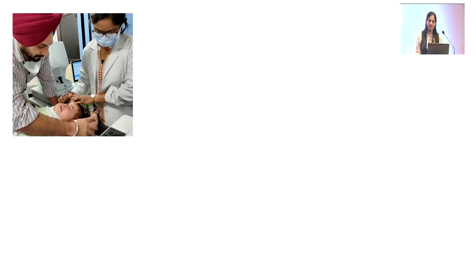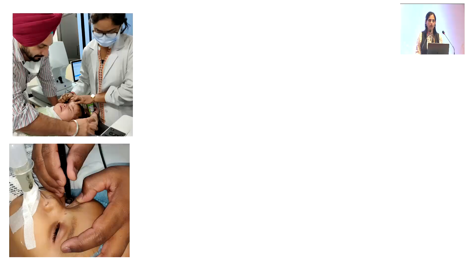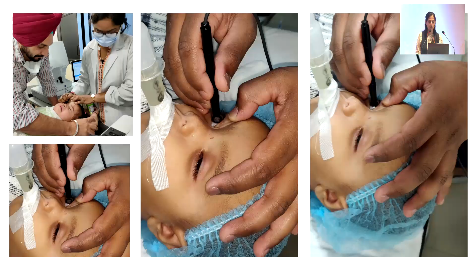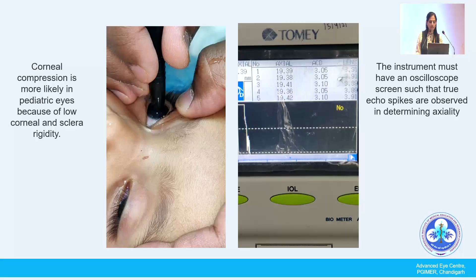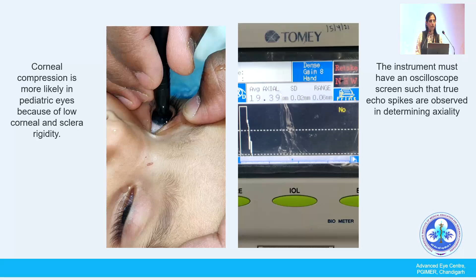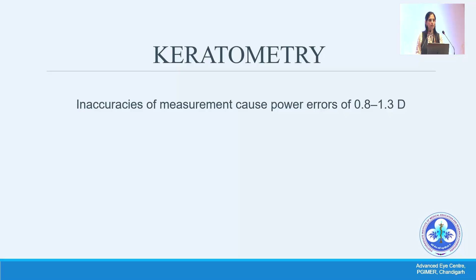In the office, the child is often crying and up-rolling, so the readings might not be very accurate. And under anesthesia, you can ensure that the eye is stable and is straight. And you can take a good reading with a contact scan also, making sure that you don't indent the cornea. Now, you have to take multiple readings because corneal compression is more likely because of low scleral rigidity. And you should always have an instrument which has an oscilloscope screen, if you can, and hear the sound. These are spikes that you're getting, and you have to look at whether they are coming from the lens, so that you know that you are looking at the correct axial length from the center of the eye.